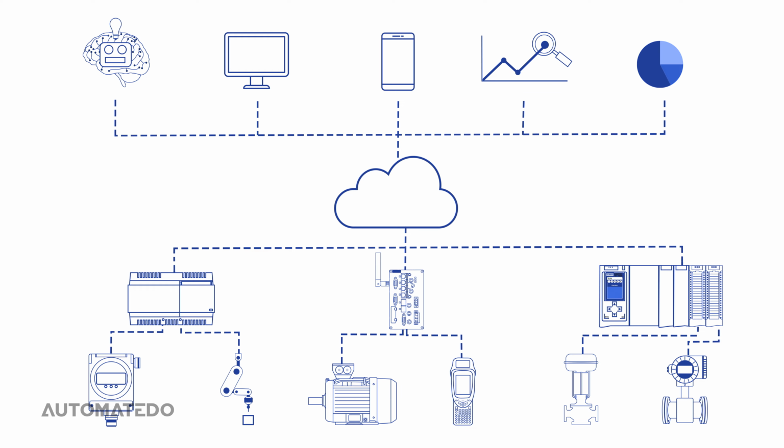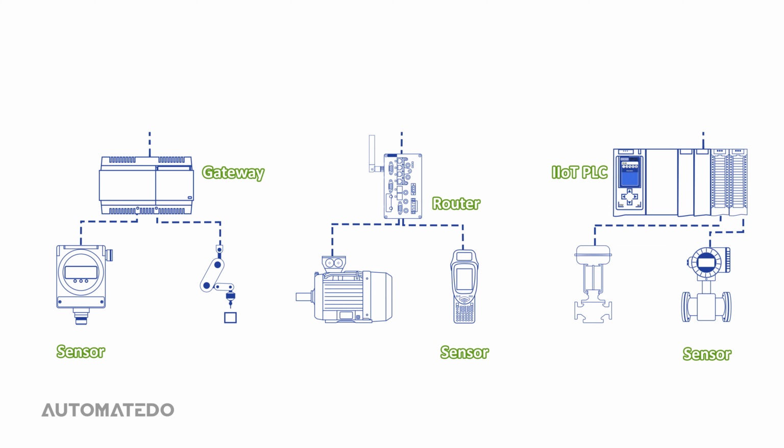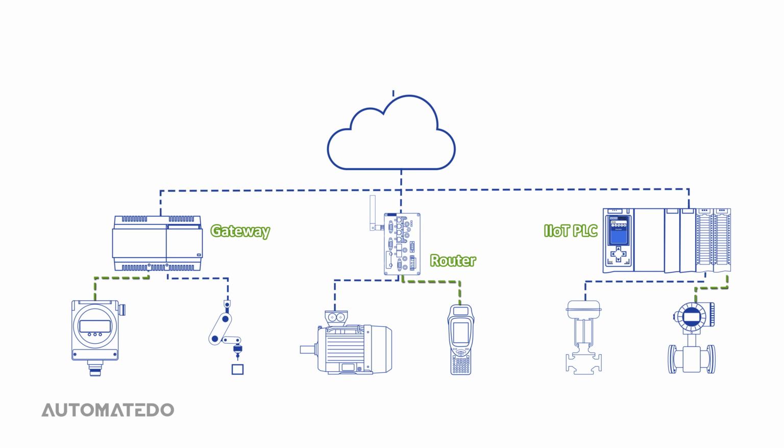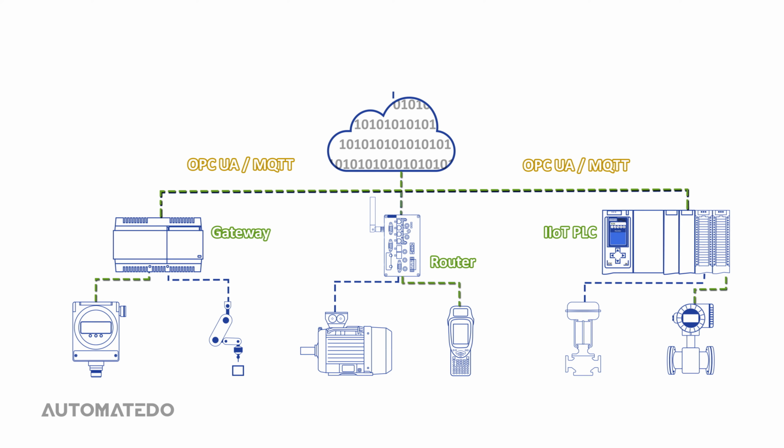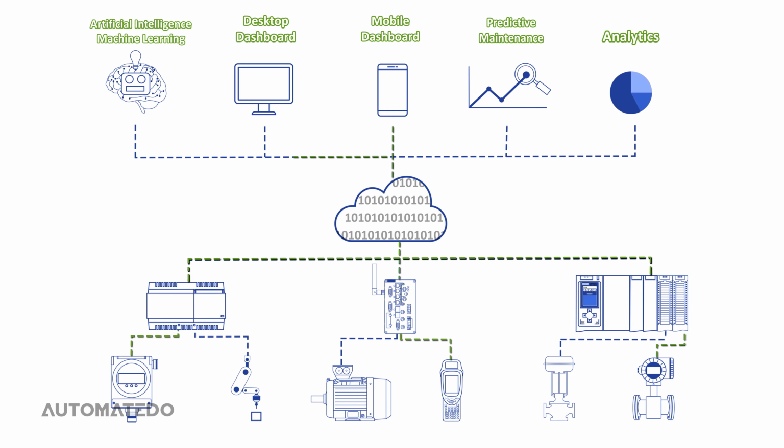Now it's time to dive deep into how the Industrial Internet of Things works and how it creates a connected solution. At the bottom of the diagram, sensors act as measurement devices to sense and capture process parameters. Data is then broadcast across a network in the factory easily to reach edge controllers. When edge controllers get data, they serve as the bridge connecting the local network to the cloud. The edge controllers use OPC UA or MQTT protocols to pass data to the cloud since they are open protocols and are manufacturer independent, which facilitates IIoT adoption and integration. After the data has been stored in the cloud, you will have the power to monitor and control operations, analyze statistics on industry performance, anticipate upcoming behavior, especially for use in maintenance, and use advanced capabilities such as machine learning and artificial intelligence.